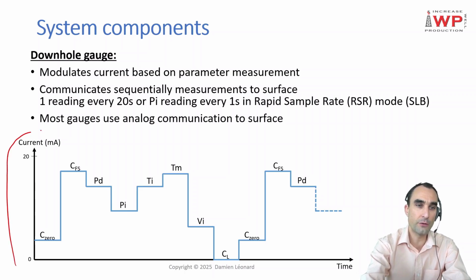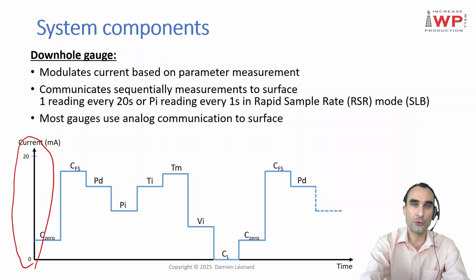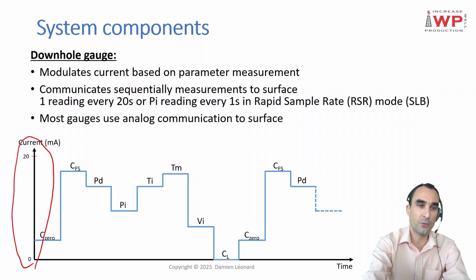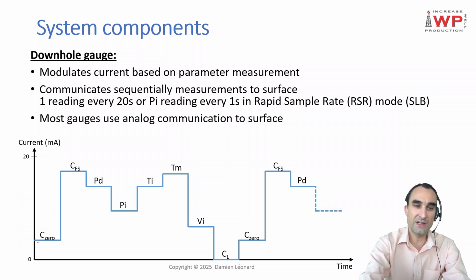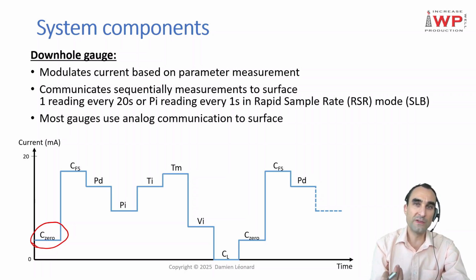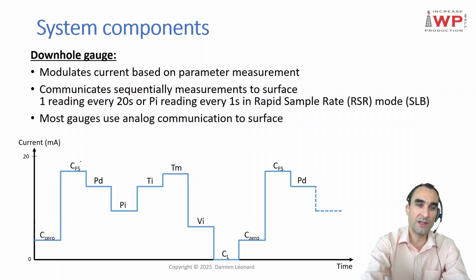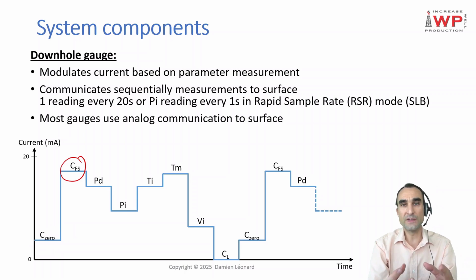How does it look? If we draw a curve, you will see something like this, where on the y-axis you've got the current being sent to the gauge by the surface panel, measured in milliamperes. The gauge will initially send the C0, the current zero. This is basically the power pulled by the gauge when no sensor is being powered. Then it will pull the CFS, the current full scale. That's the maximum current being pulled by your gauge.